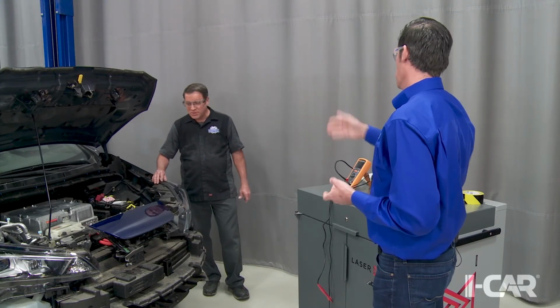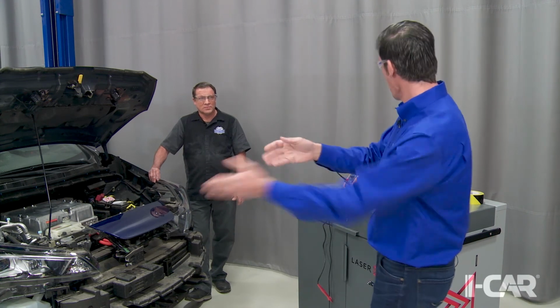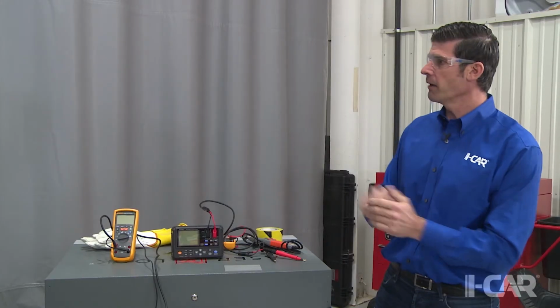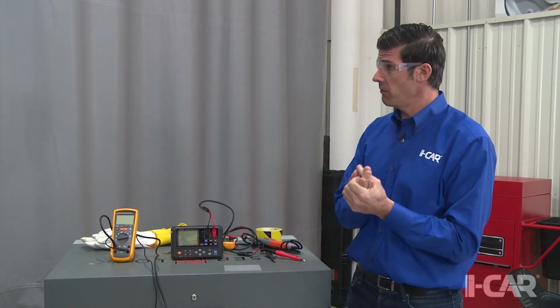What is your body resistance? You have an idea? Probably right now my outer skin resistance is pretty high because my skin's so dry, but internally it's relatively low. We say about 1,000 ohm. That's a typical body resistance when you would get a shock, coming into your hand and maybe going through my body onto the ground where I'm standing. We talk about 1,000 ohm body resistance. What do you think is the resistance of this nice thick cable? I would think that'd be extremely low. Okay, where is electricity going? Towards the lower resistance. That means if a housing had 400 volts due to an insulation error and I touched it, this would save my life.